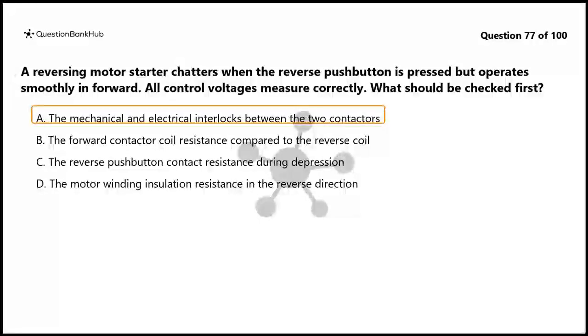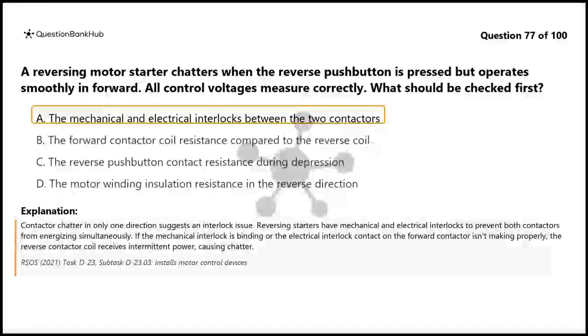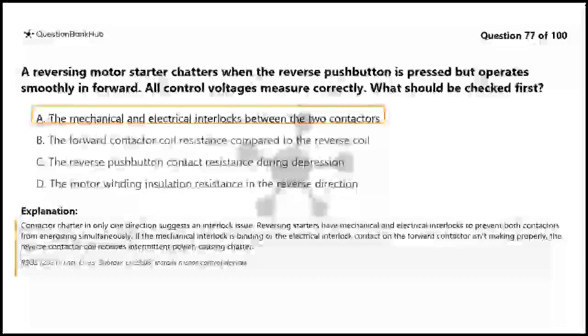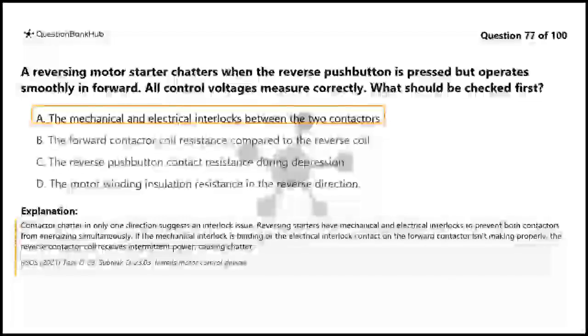The correct answer is A. The mechanical and electrical interlocks between the two contactors. Contactor chatter in only one direction suggests an interlock issue. Reversing starters have mechanical and electrical interlocks to prevent both contactors from energizing simultaneously. If the mechanical interlock is binding or the electrical interlock contact on the forward contactor isn't making properly, the reverse contactor coil receives intermittent power, causing chatter.